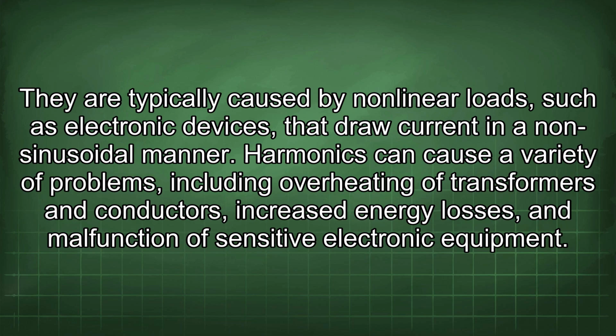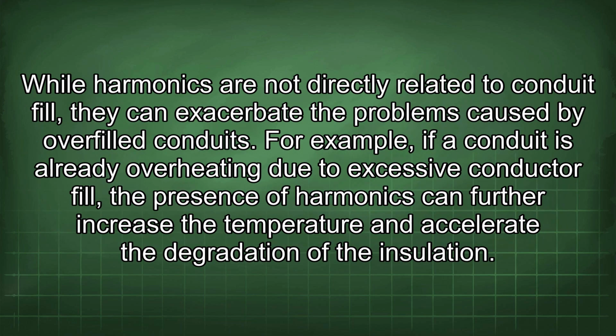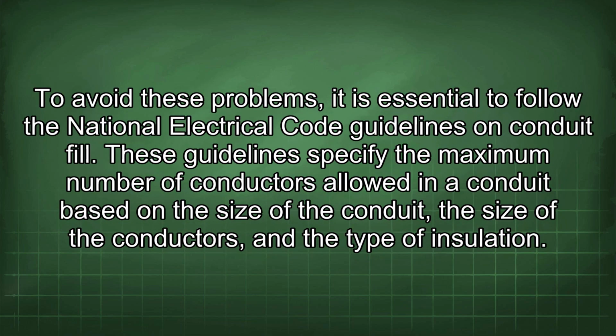Harmonics can cause a variety of problems, including overheating of transformers and conductors, increased energy losses, and malfunction of sensitive electronic equipment. While harmonics are not directly related to conduit fill, they can exacerbate the problems caused by overfilled conduits. For example, if a conduit is already overheating due to excessive conductor fill, the presence of harmonics can further increase the temperature and accelerate the degradation of the insulation. To avoid these problems, it is essential to follow the National Electrical Code guidelines on conduit fill.